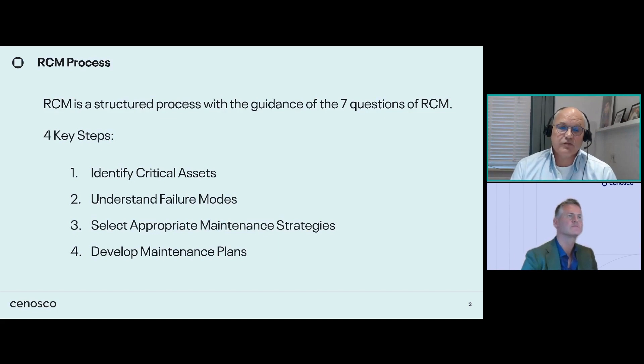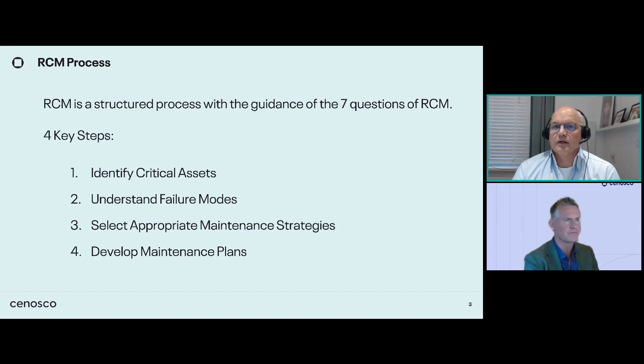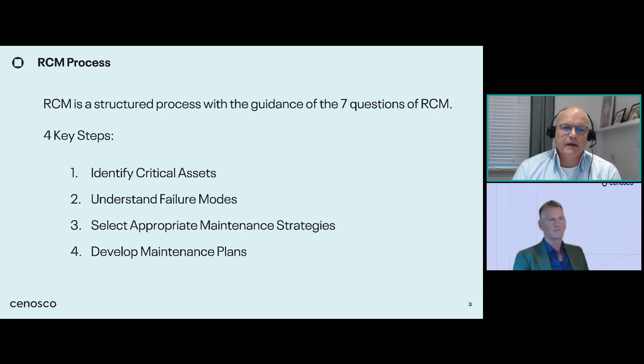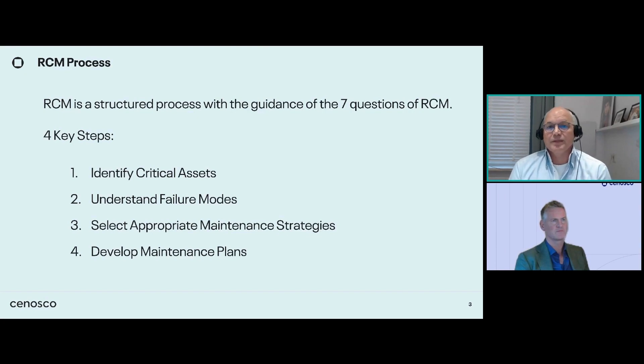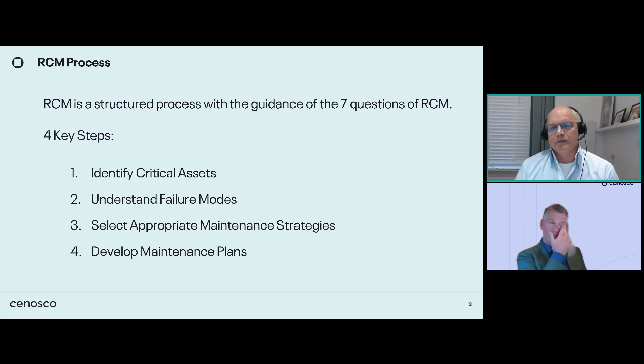Based on the analysis of failure modes, RCM helps organizations choose the most suitable maintenance strategy. This is driven by the characteristics of the failure mode — for instance, whether degradation is age-related or non-age-related, and whether consequences make themselves known or are hidden. Part of the maintenance strategy selection is a verification of its effect: given the degradation and the maintenance strategy provided, what will be the effect of that failure mode, and would it actually occur again? This gives an estimate of what we call the residual risk. Preventive maintenance tasks are not always executed as perfectly as expected, which must be taken into account.